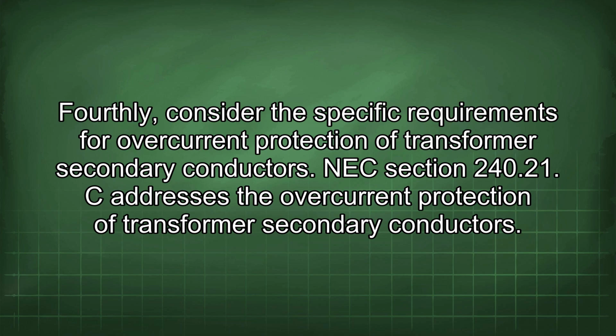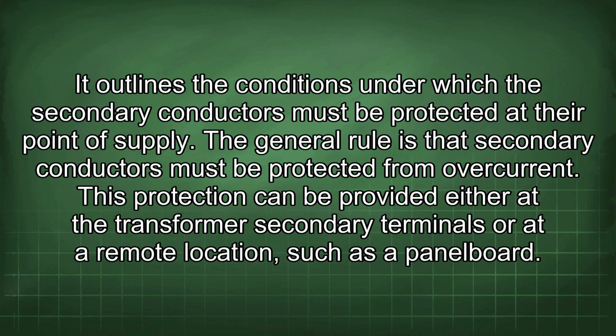Fourthly, consider the specific requirements for overcurrent protection of transformer secondary conductors. NEC Section 240.21(C) addresses the overcurrent protection of transformer secondary conductors. It outlines the conditions under which the secondary conductors must be protected at their point of supply. The general rule is that secondary conductors must be protected from overcurrent. This protection can be provided either at the transformer secondary terminals or at a remote location, such as a panelboard.